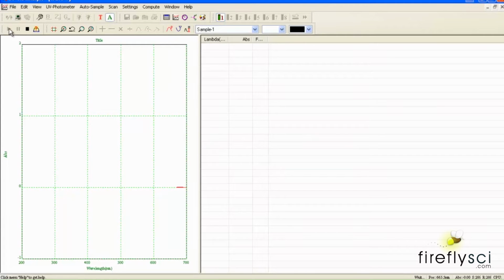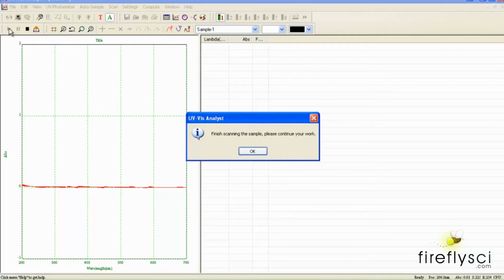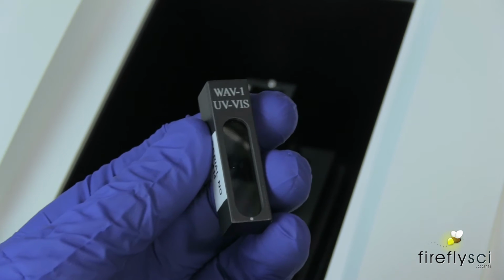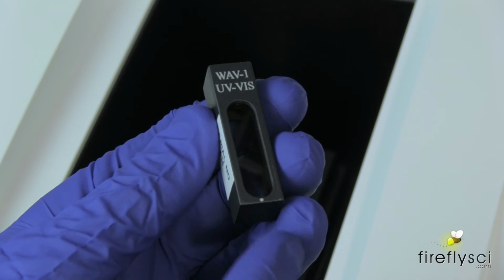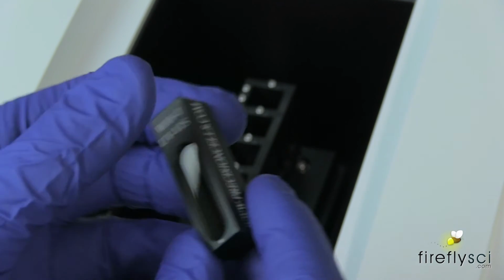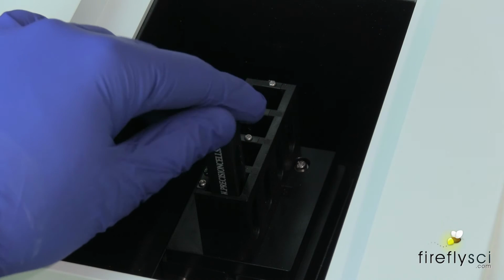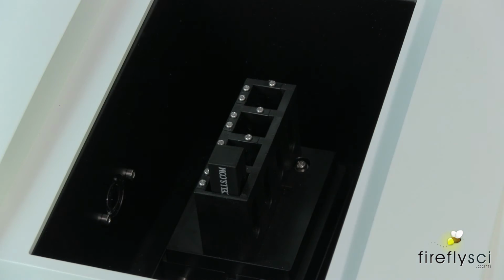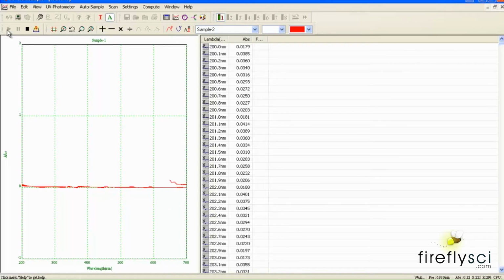Now we'll just do a baseline scan to make sure that the machine is reading at 0. For the baseline scan, we have to make sure that there is nothing in the cell holder. Once the baseline scan is done, we can insert the WAV-1 UV Vis filter. When placing the WAV-1 filter in the machine, you have to remember that the white dot faces the direction of the light beam. Let's hit the old start button and see what we get.